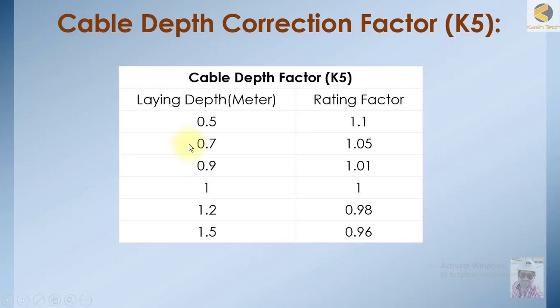Then we have another correction factor called the depth factor — how deep you are burying the cable underground. As the depth increases, the cable will be more derated. You can see that at 0.5 meters depth the correction factor is 1.1, at 0.7 meters it reduces to 1.05, at 0.9 meters it comes to 1.01, at 1 meter it is 1, and at 1.2 meters it goes down again. This is the cable depth correction factor K5.